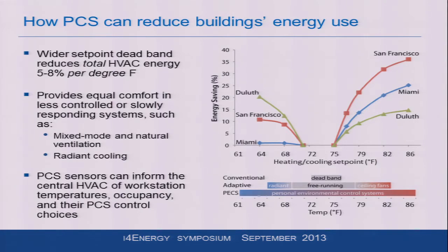And then the comfort is good, and because it expands the set point, you can then enable more efficient types of HVAC systems on new buildings. At least you could allow naturally ventilated buildings, or buildings that had cooling towers instead of chillers, or buildings that had evaporative cooling systems or radiant cooling, which might be very slow acting. It might be cold in the morning. Well, if you've got the Footwarmer to take care of that problem for an hour or two, then that type of building will work, and then you can save energy by designing those kinds of buildings instead of VAV buildings.